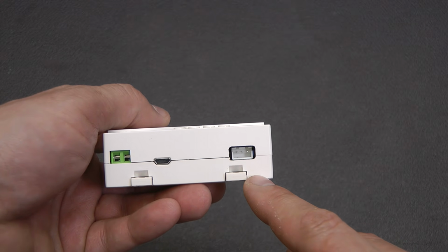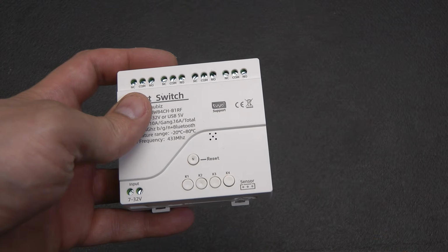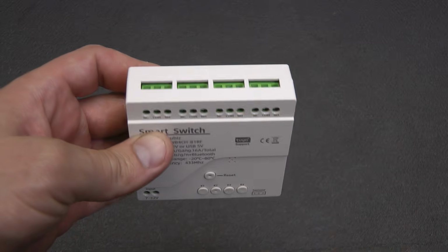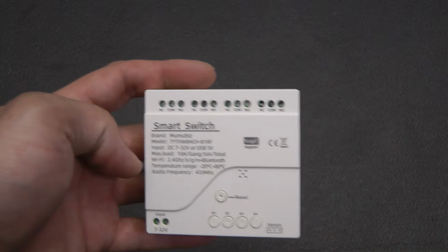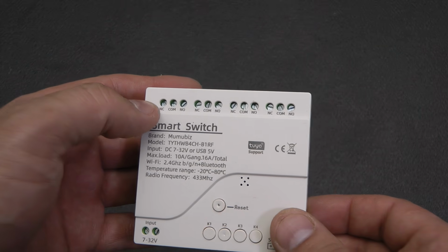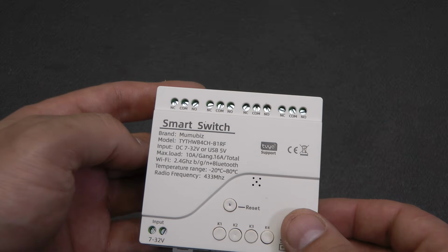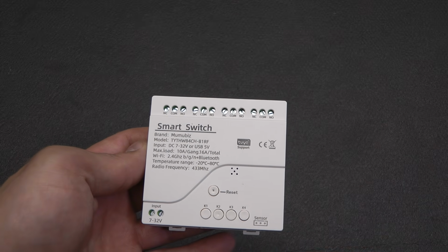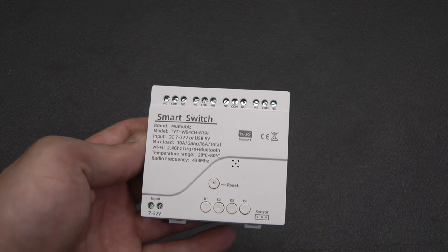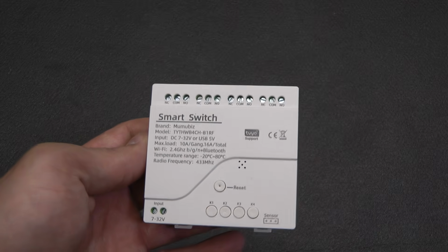In the lower right corner, there is a connector for an external temperature sensor or temperature and humidity sensor. At the top, there are 4 independent relays with dry contacts: common, normally open, and normally closed. I have already explained such contacts in detail in a separate video. I will leave a link in the description, so we will not stop on this topic here.